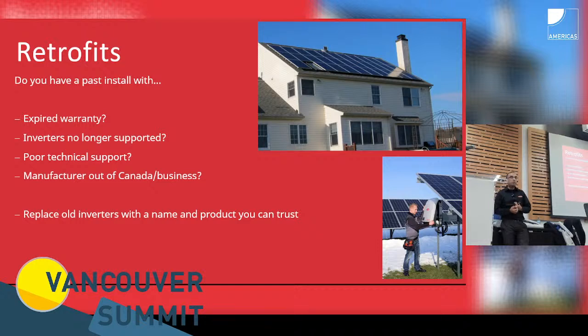And one last thing you always want to do—I told you about insulation failure and isolation tests—is always do your isolation tests on any PV panel you're going to retrofit with a newer inverter, and do them under certain weather conditions. The reason being, just because you've got a nicked wire or a broken PV panel doesn't mean you have a ground fault.